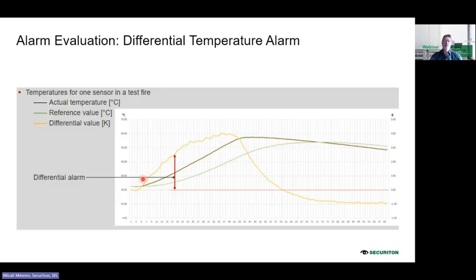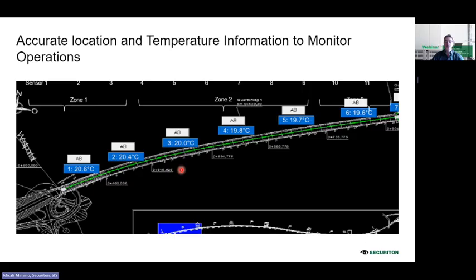We have here the reference value. We have the black line here, which is the actual temperature that we have at the moment, for example, in a tunnel. And then we have, during a fire, the differential value. This is the increase. And here we can configure, we can decide how fast the system or the sensor has to detect. One example can be 0.5 degrees in 1 minute. So if we have these conditions, the system may trigger an alarm. And so we are able to program every sensor with a different value.